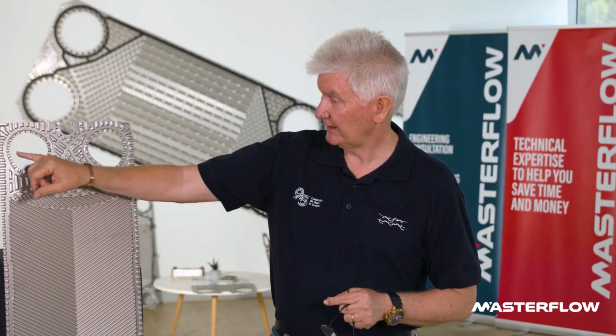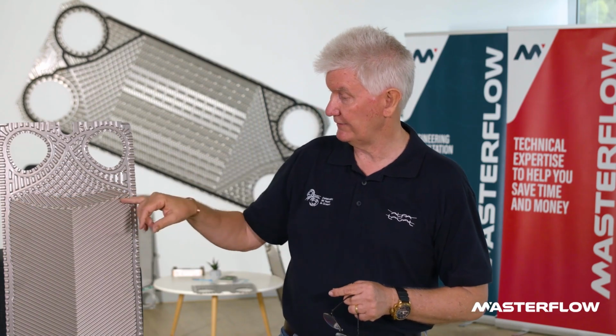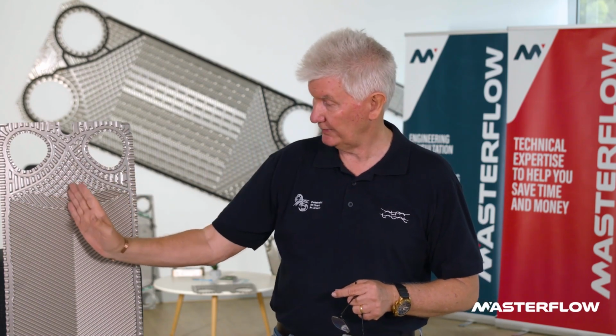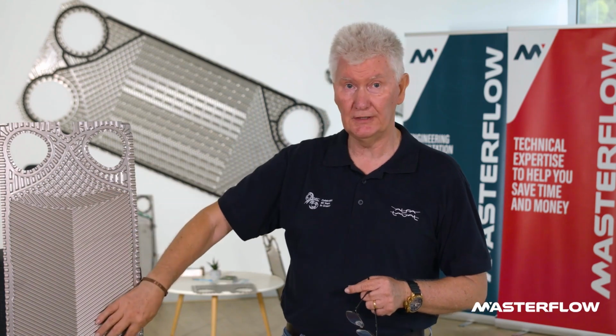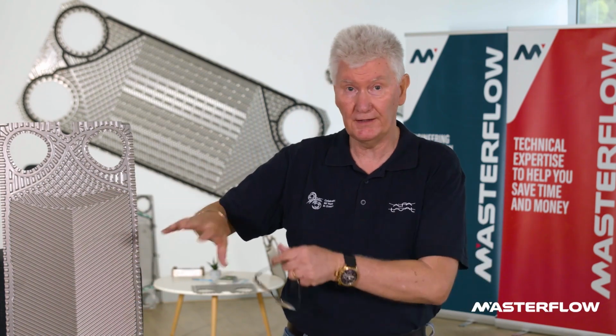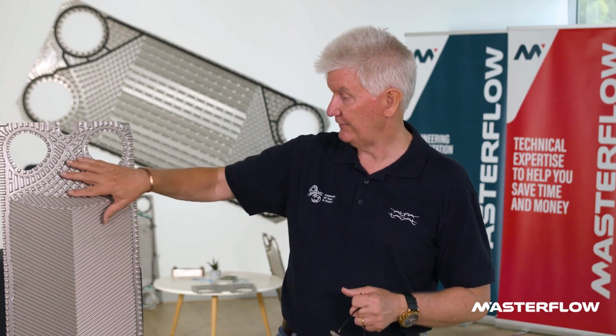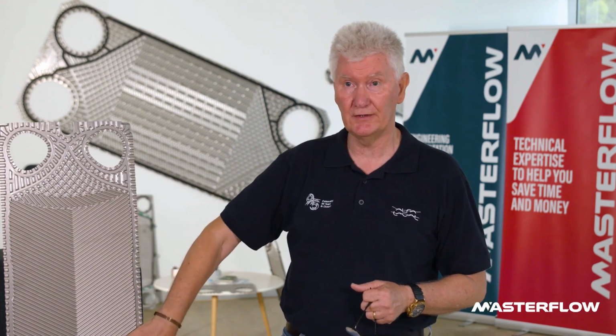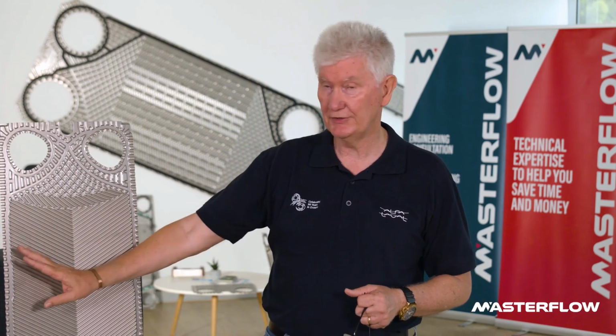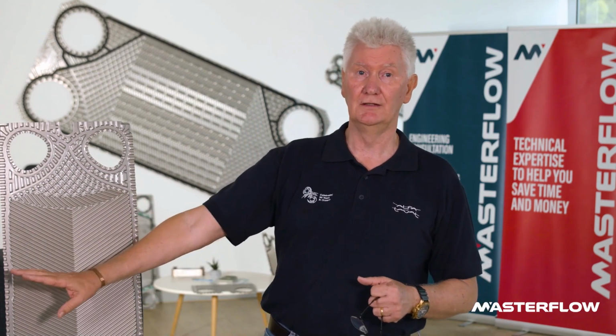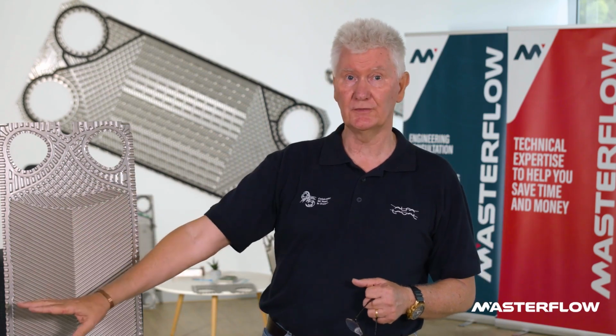And we can show how fouling starts. As your velocity through the heat exchanger decreases, the fluid that comes in here, instead of going right across the face of the plate, tends to go down just one side. So you have little or no flow down this side of the plate. You're not filling it up at low pressure drops. So fouling starts to take off on this side of the plate and then moves across. So eventually you block the channel when you've got such low pressure drops.